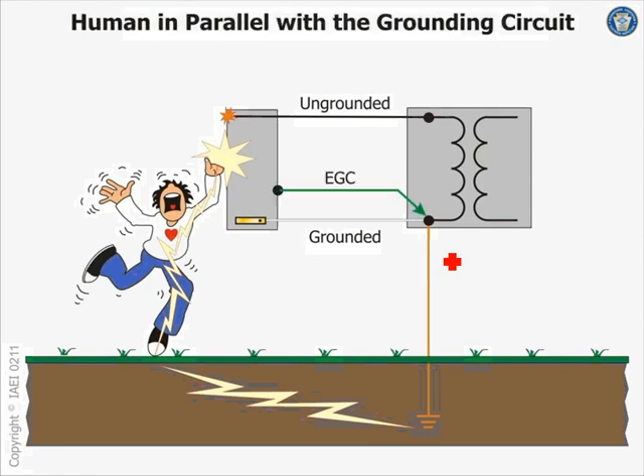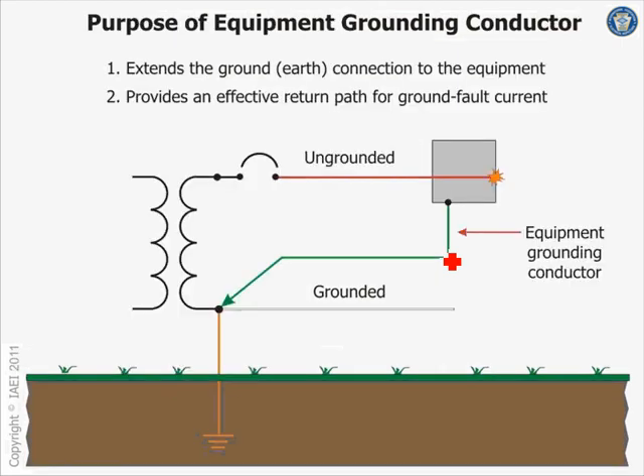So if you have an equipment ground conductor, the equipment ground conductor will trip the circuit before you go grab into it. You'll know that this equipment is faulted before you go touch it, because the circuit breaker will trip, and now this equipment is not working. That's the principle of operation of the equipment ground conductor, extended ground with the earth.